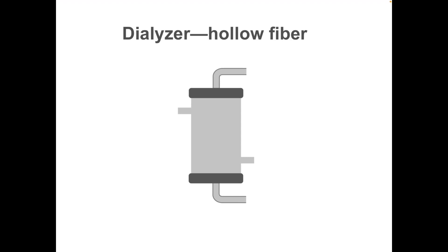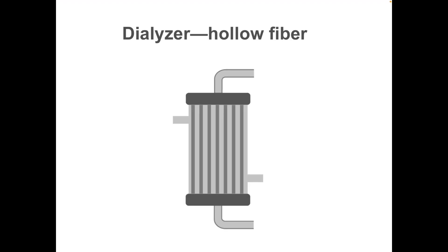The dialyser is basically an instrument that has many hollow fibers inside it through which the blood passes. The hollow fibers generally have an internal diameter of around 180 to 200 microns and a wall thickness of around 30 to 40 microns. These are the various hollow fibers. Here is a 2D view — actually these are arranged in 3D, like you can see from the outside, multiple fibers are arranged so that it forms a cylindrical device.